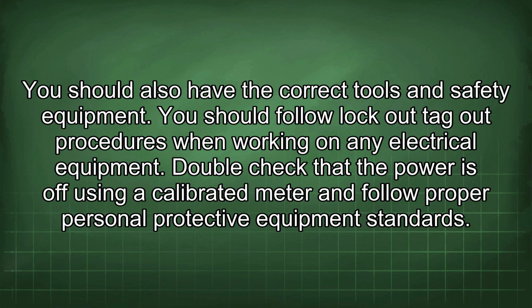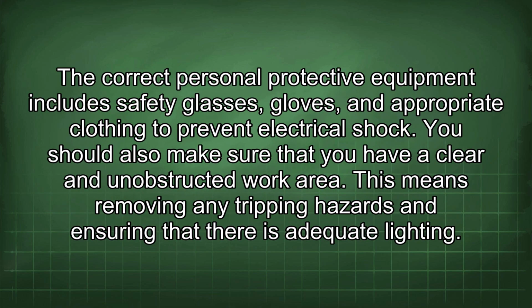You should follow lockout-tagout procedures when working on any electrical equipment. Double check that the power is off using a calibrated meter and follow proper personal protective equipment standards. The correct personal protective equipment includes safety glasses, gloves, and appropriate clothing to prevent electrical shock. You should also make sure that you have a clear and unobstructed work area. This means removing any tripping hazards and ensuring that there is adequate lighting.